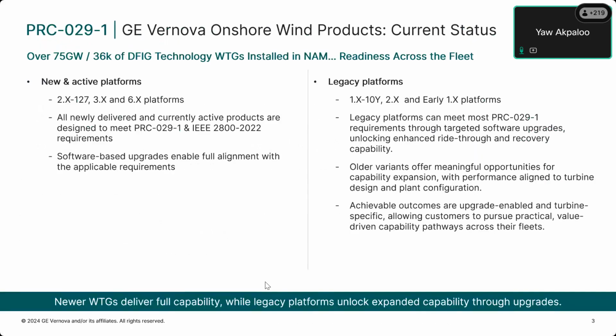So when we look at the legacy fleet, the story is still very constructive across our 1X, 2Xs, and early 1X platforms. Most requirements are achievable through targeted software upgrades. For the older variants, capability expansion is very real. It's just aligned to turbine design and configuration. So the key message here is this: across the fleet, there is a clear upgrade-enabled path to enhance grid capability, and it's not one-size-fits-all, but it's a practical and scalable movement.